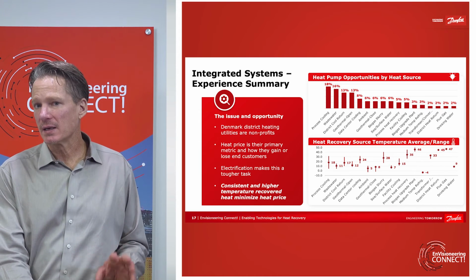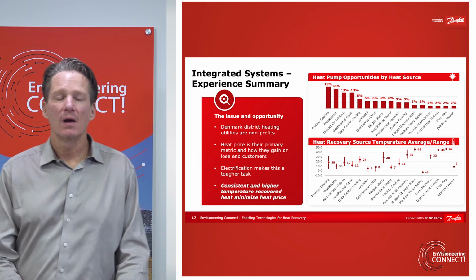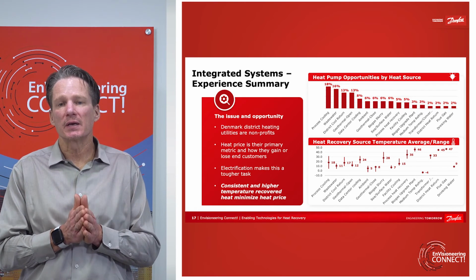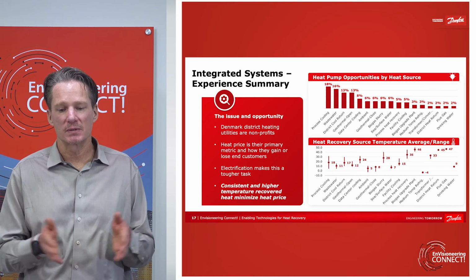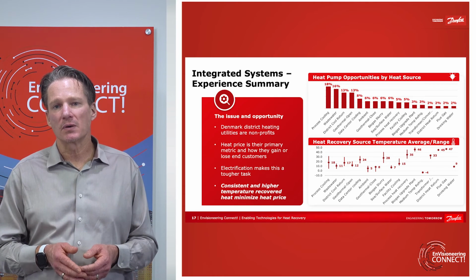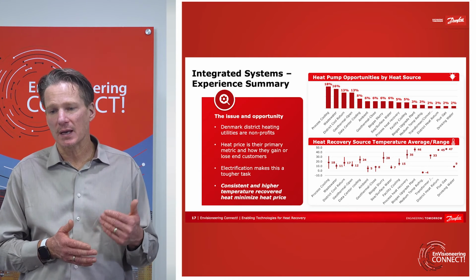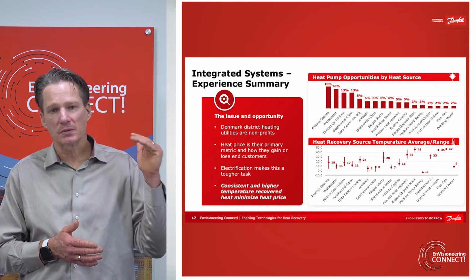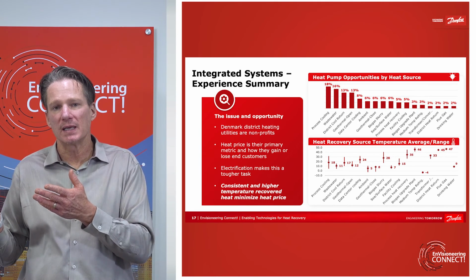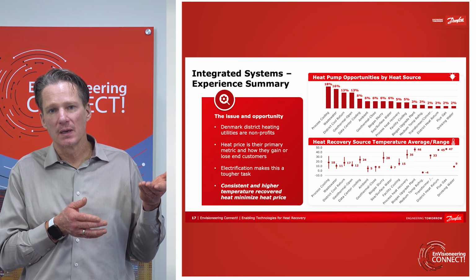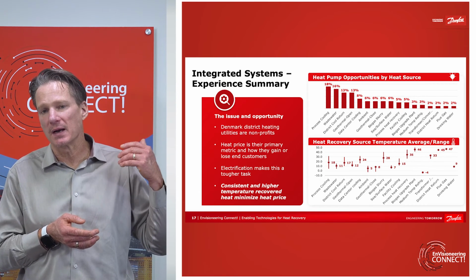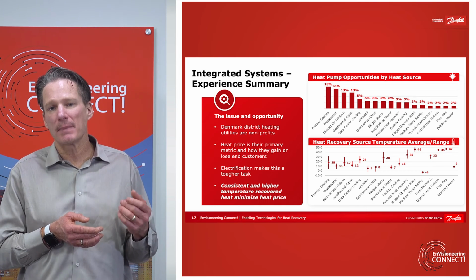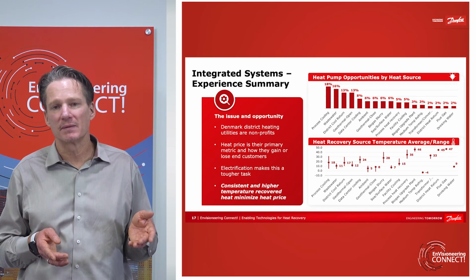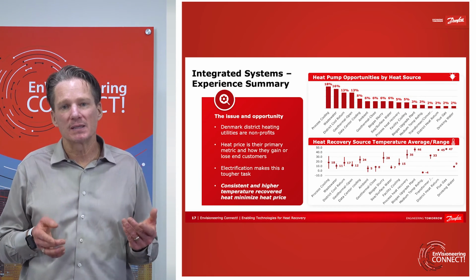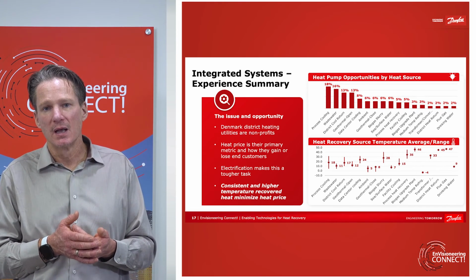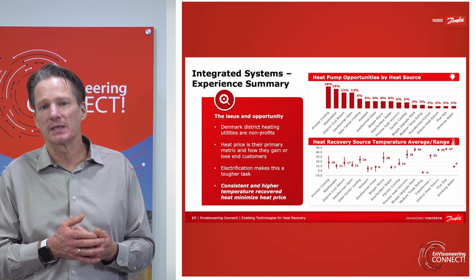And this is an overall summary. So again, the main takeaways: the best opportunity that we found based on our work in sector integration over the last couple years to integrate water-to-water heat pumps into systems to tie them together and electrify their heating system, the best opportunities are these critical facility cooling systems. But what drives that is a combination of factors. You have a relatively constant load on those critical facility cooling systems, meaning a relatively constant recovered heat capacity. It's operating at a higher cooling temperature, which means that that water-to-water heat pump that you're utilizing to provide that heat is going to operate extremely efficiently. And you also have a backup power system on each one of those facilities, meaning that it basically has no risk of availability. All of that means also that it's going to be the lowest cost, in the case of a district heating utility, lowest cost future base load decarbonized heat source for that district utility.